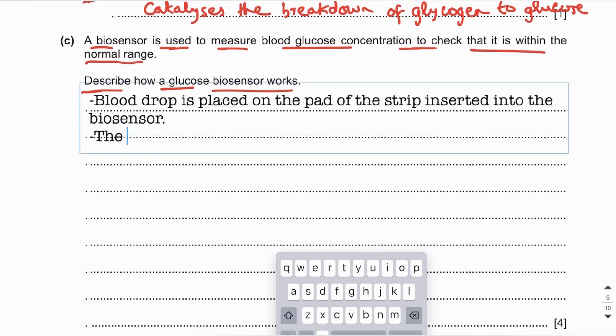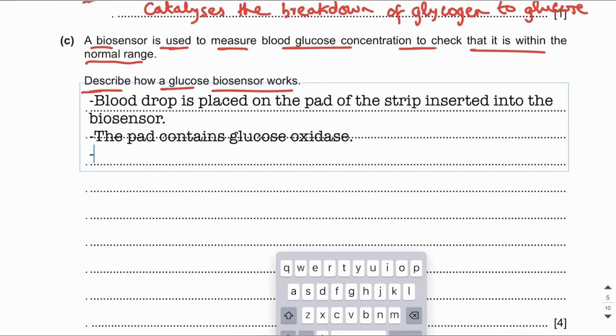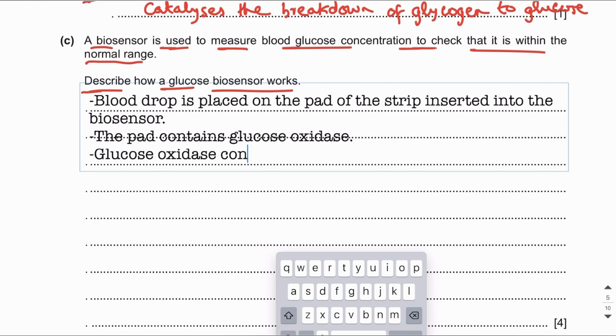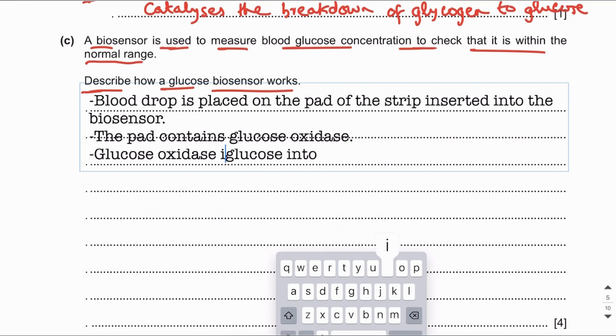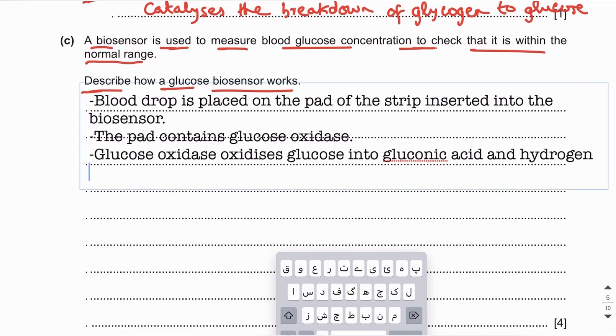The pad contains the enzyme glucose oxidase. Glucose oxidase oxidizes glucose into gluconic acid and hydrogen peroxide. This is the reaction that glucose oxidase catalyzes when the blood sample is applied to the pad.